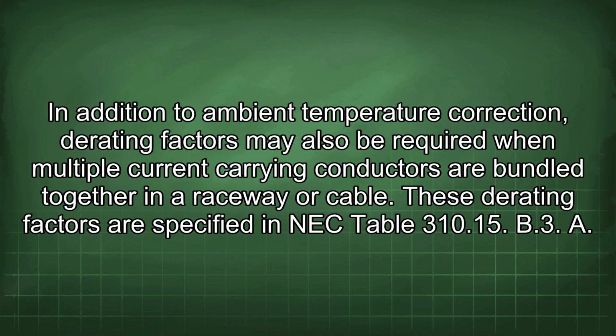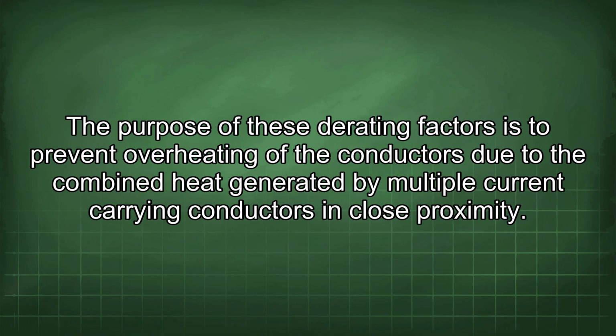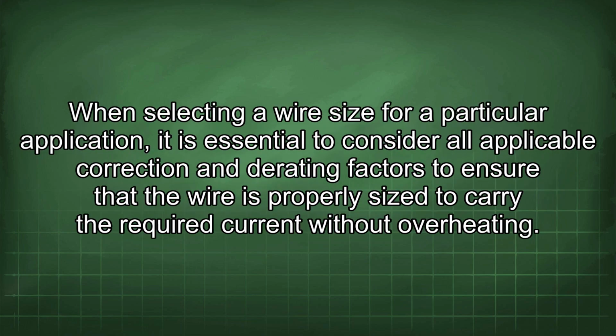In addition to ambient temperature correction, derating factors may also be required when multiple current-carrying conductors are bundled together in a raceway or cable. These derating factors are specified in NEC Table 310.15(B)(3)(a). The purpose of these derating factors is to prevent overheating of the conductors due to the combined heat generated by multiple current-carrying conductors in close proximity. When selecting a wire size for a particular application, it is essential to consider all applicable correction and derating factors to ensure that the wire is properly sized to carry the required current without overheating.